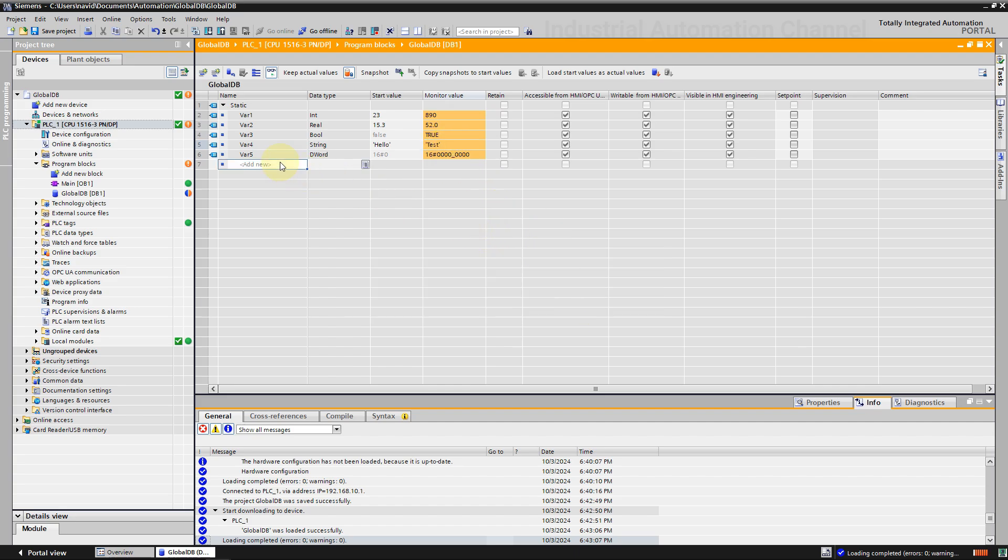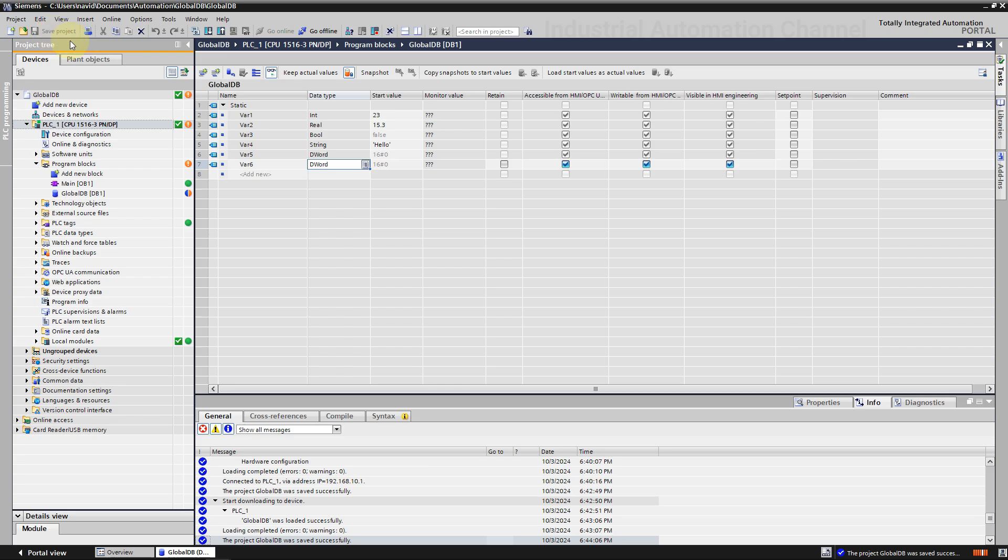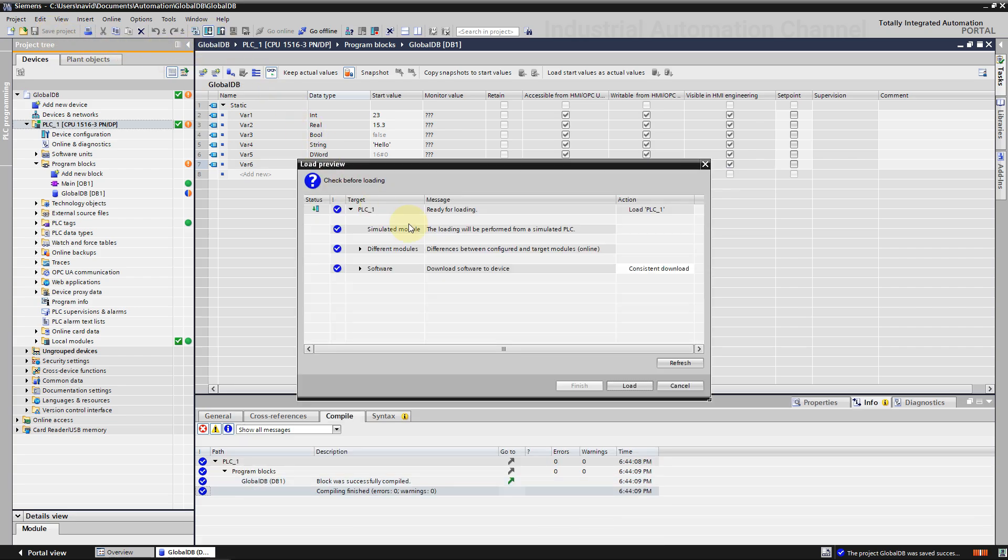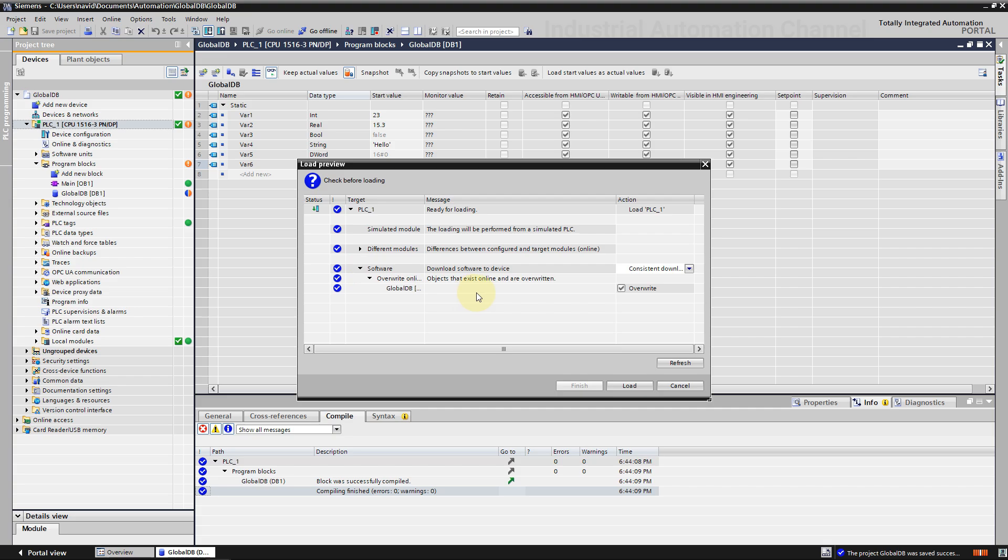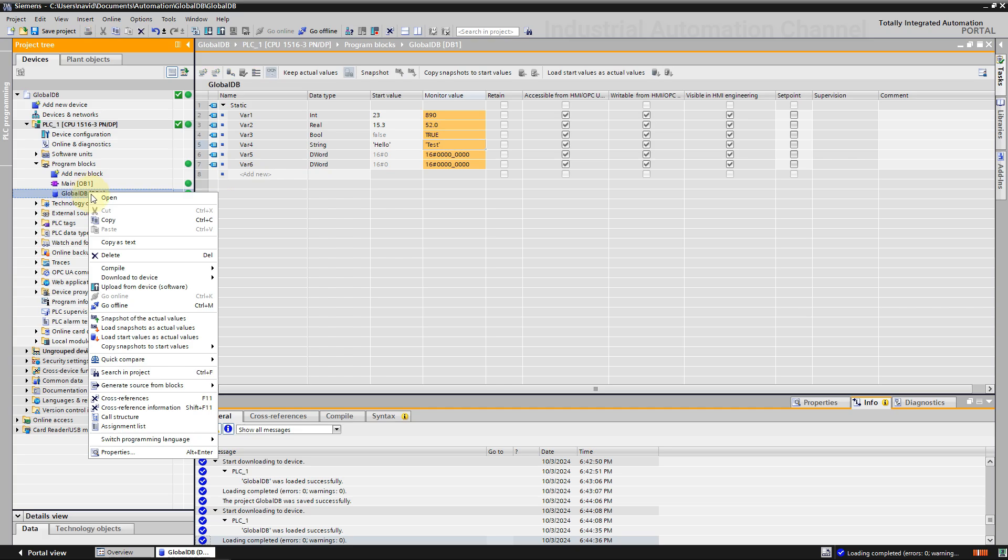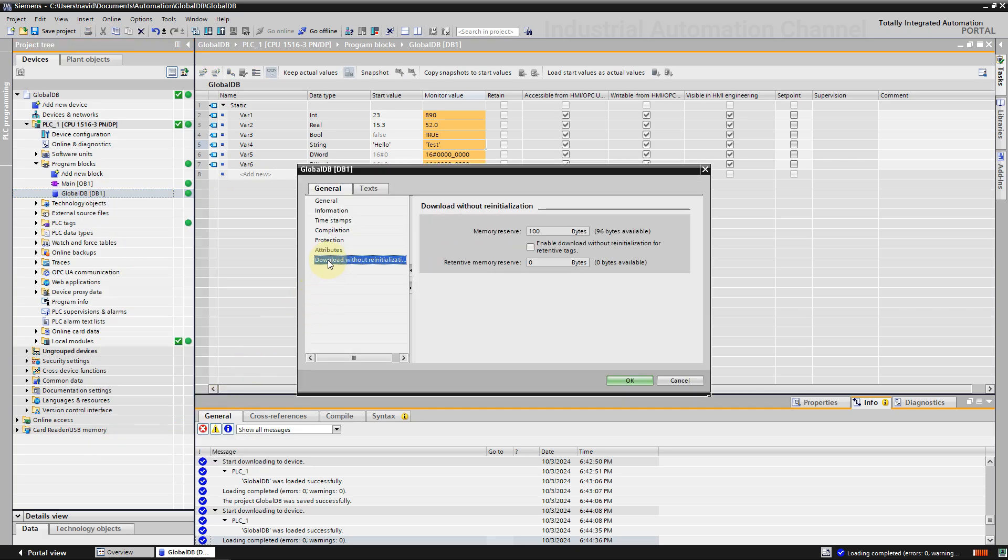As you see, the values that I changed are reinitialized and initial values are written to the variables. To avoid that we can activate memory reserve, confirm the activation, modify the values. Now define another variable and download the change. This time the download will be consistent and the values are not reinitialized. Be careful, not all the CPUs have this option, and as I said, you can download a limited size of changes. If you right click on DB and open properties, you can see and change the size of the memory reserve for this DB.